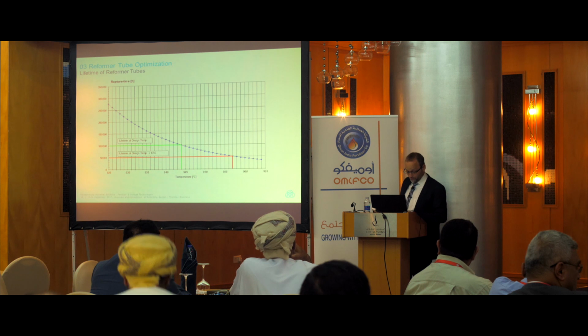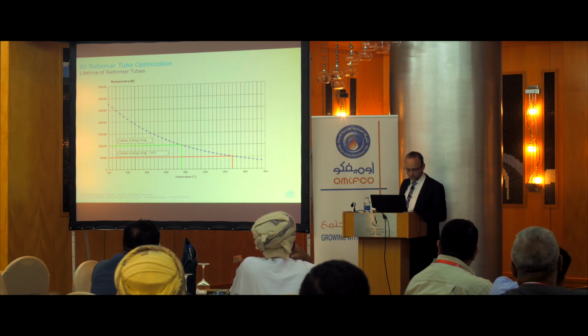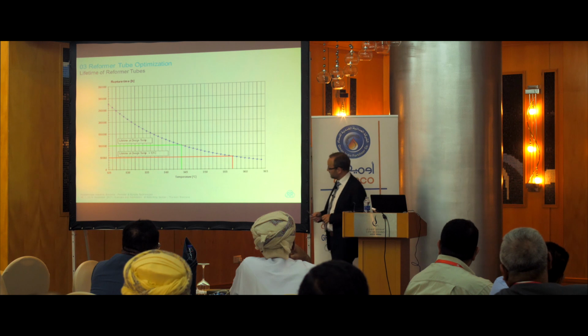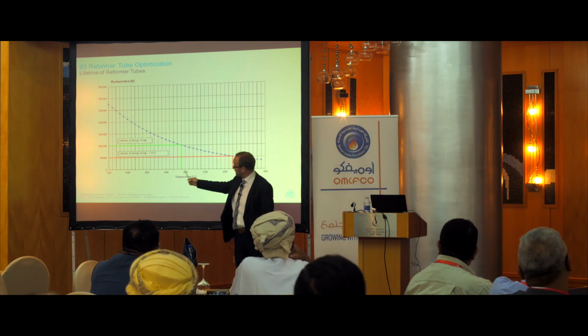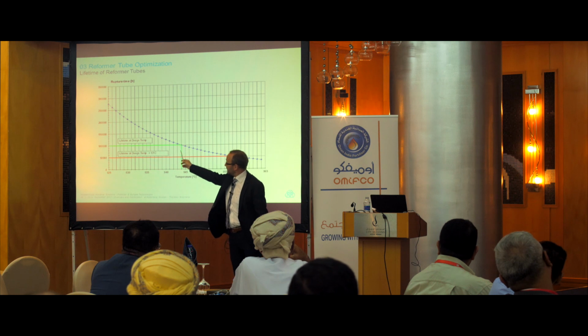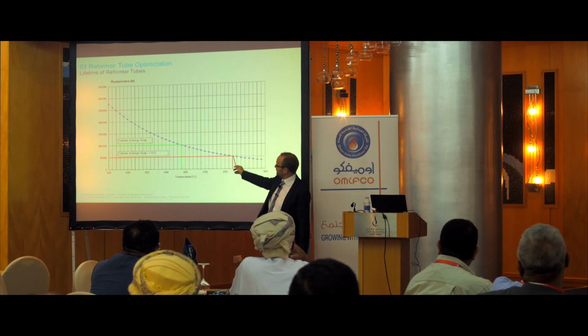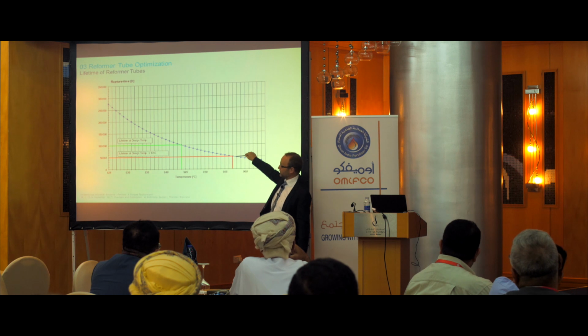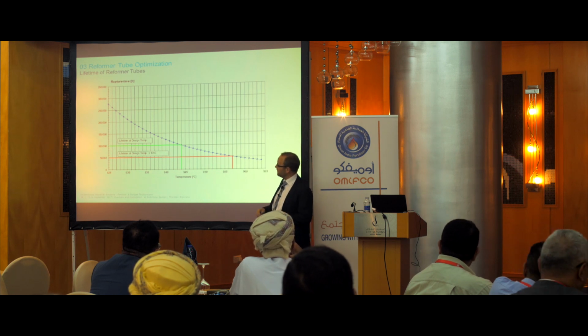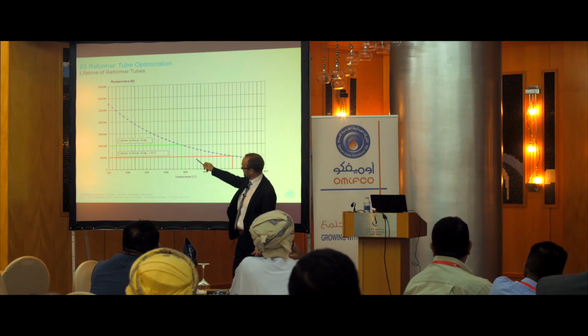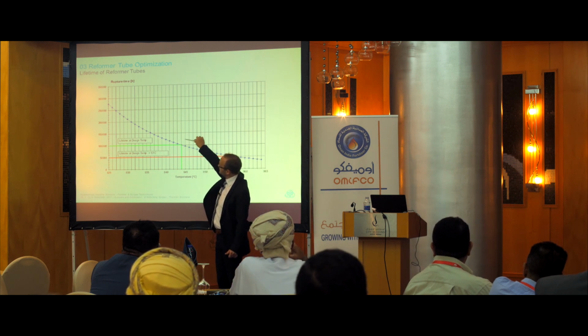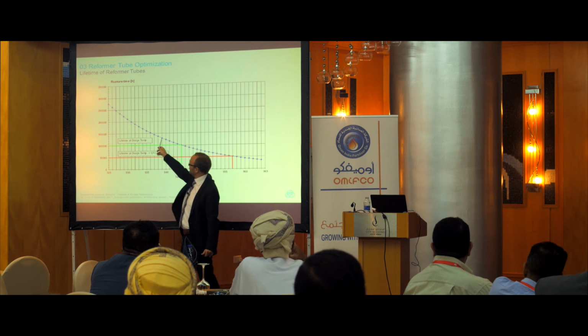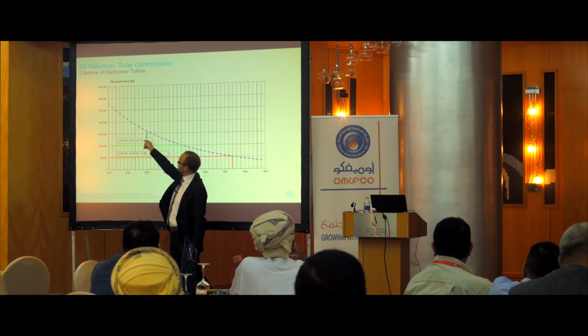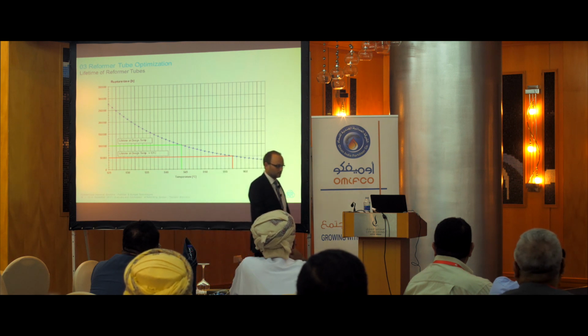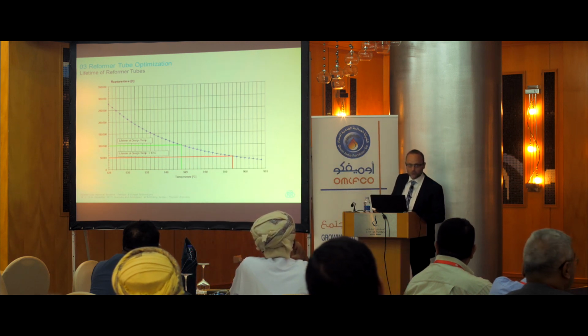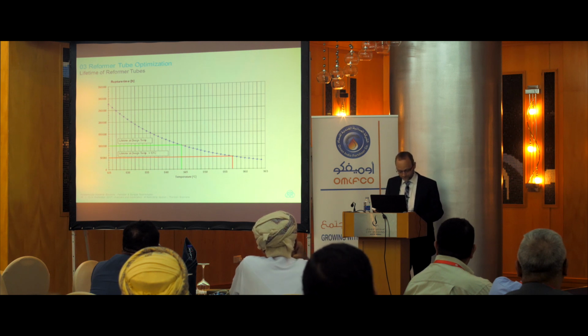As can be seen here on this curve, generated by Larson-Miller parameters, an increase of only about 13 degrees C from the design point with 100,000 hours would lead to approximately half the lifetime already. On the other hand, when you have some extra wall thickness available, the lifetime will increase dramatically. So that's the reason at some UDE reformers, the reformer tubes are running for 25 years without any failure.